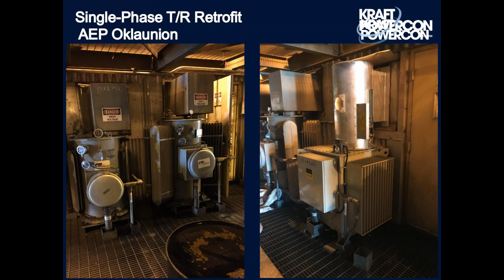and put in a new one, and keep this precipitator functioning, because we were mindful of the dimensions, not only of the bus duct and how it fit to the bus duct, but also of how the incoming power wires connected to the TR. So you'll notice none of the conduit had to be cut significantly to cause an issue. And the power supply fit up. The customer was able to do this on an outage, and we were able to make it fit so that he could do it as inexpensively and easily as possible.